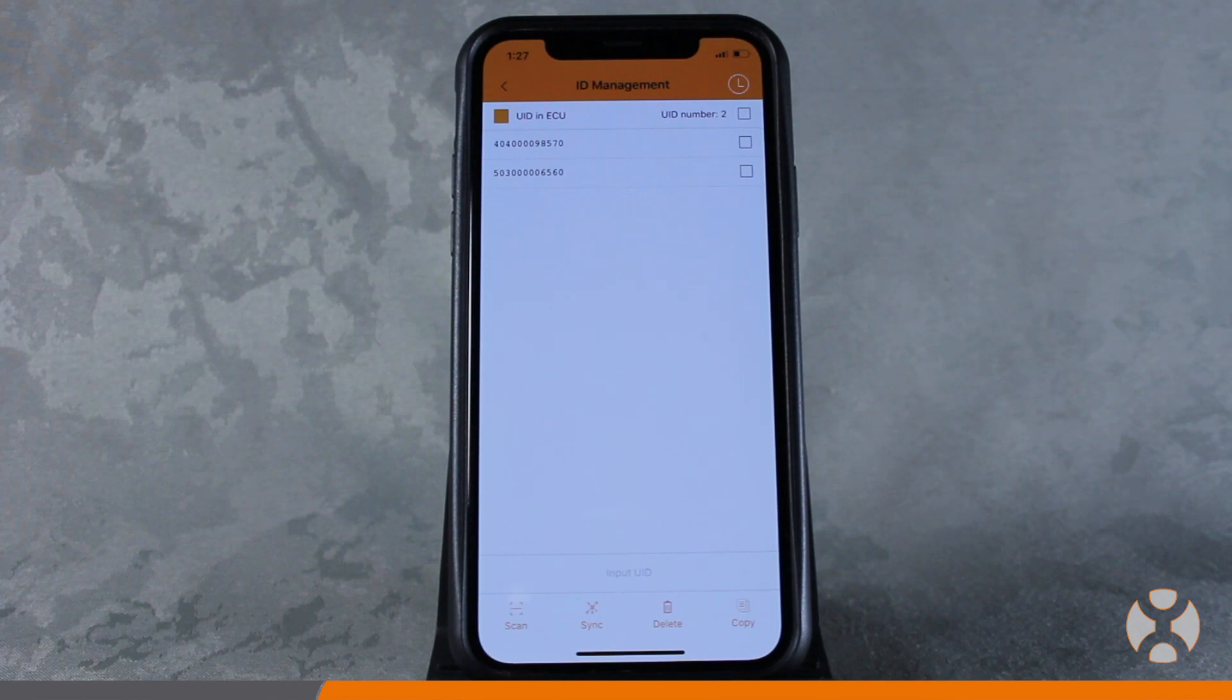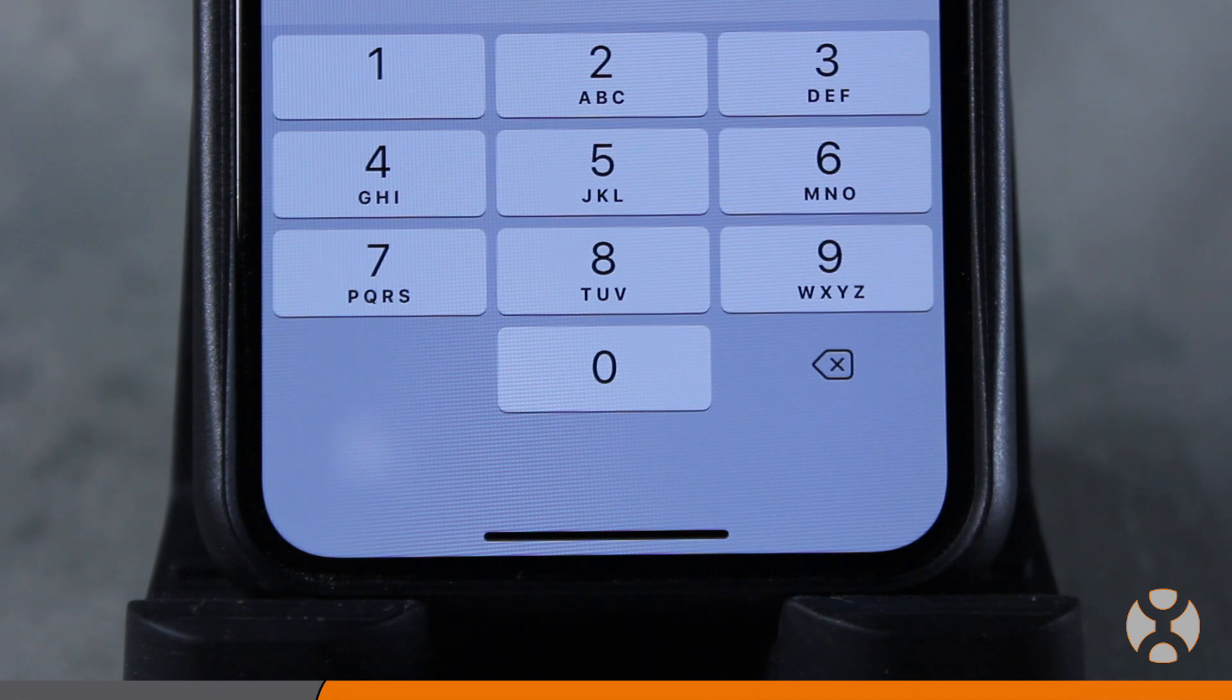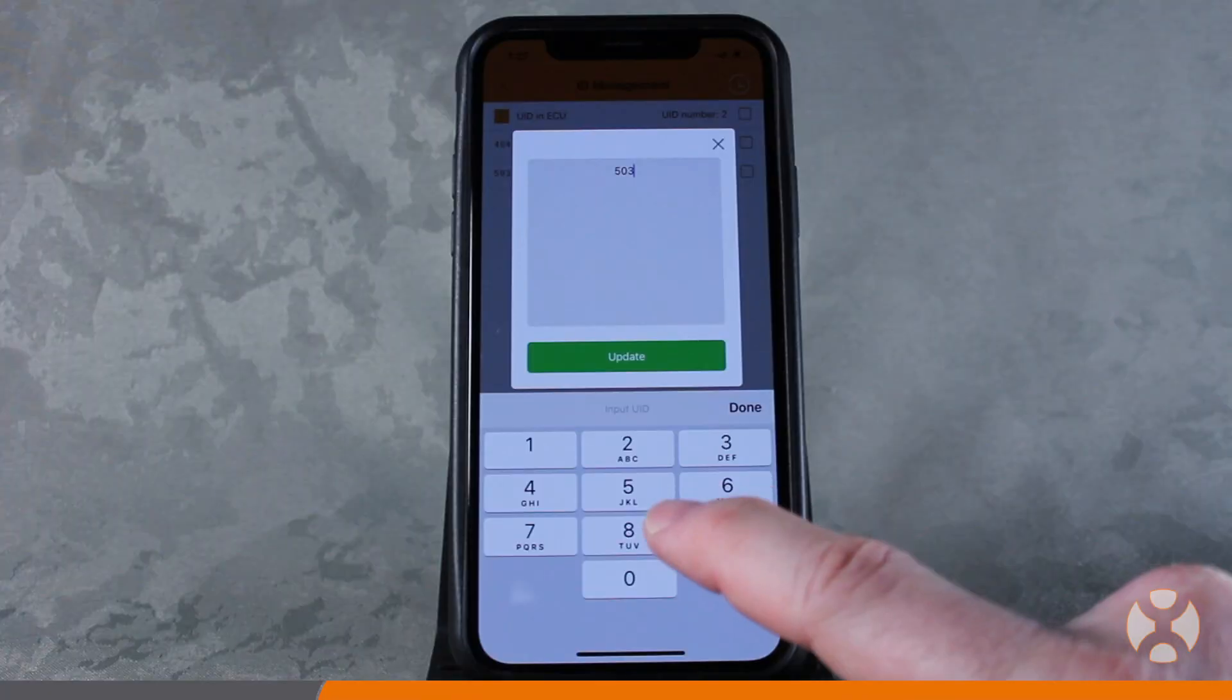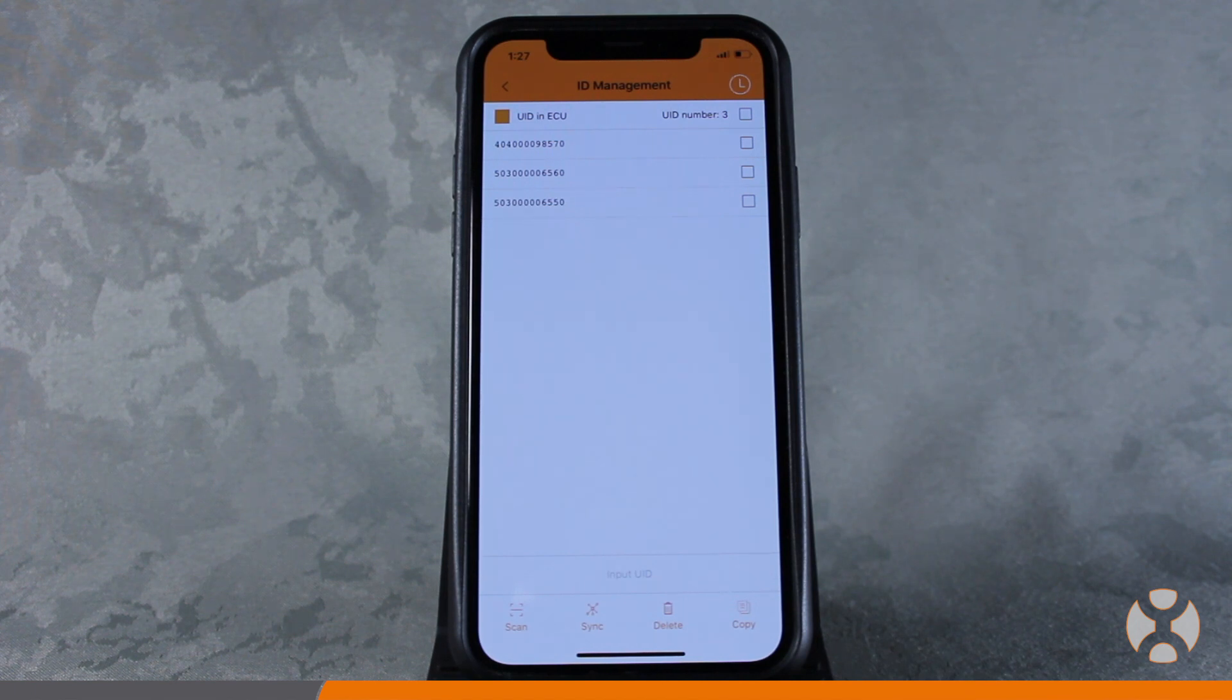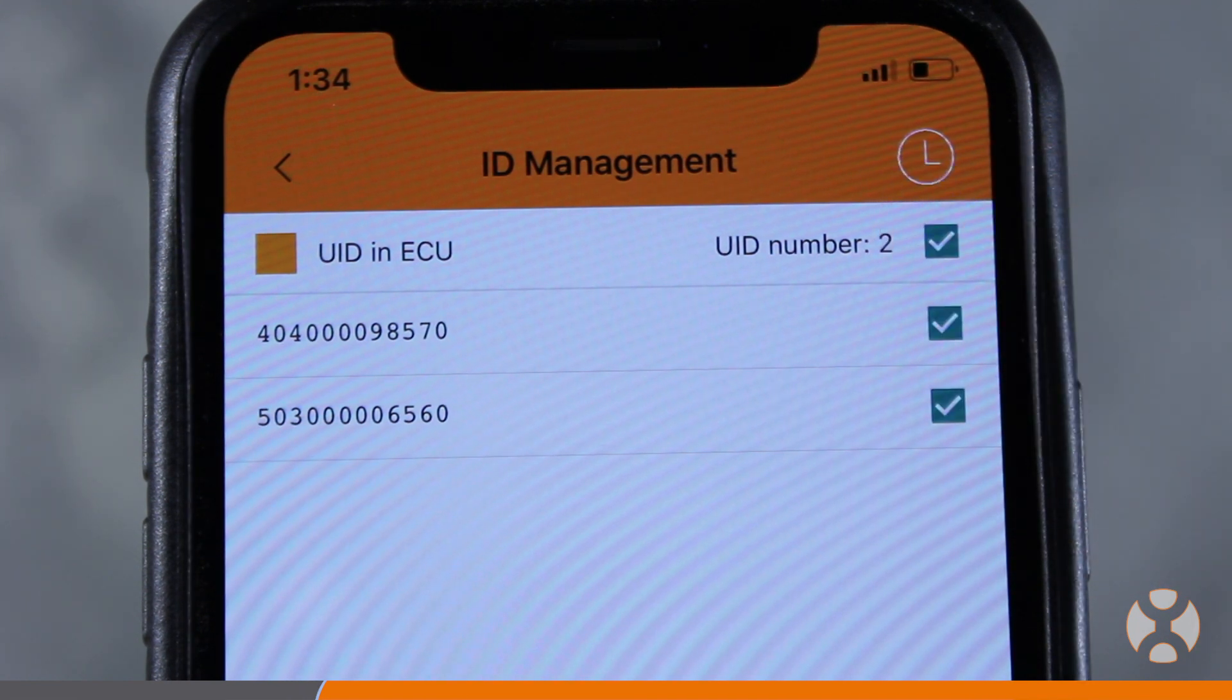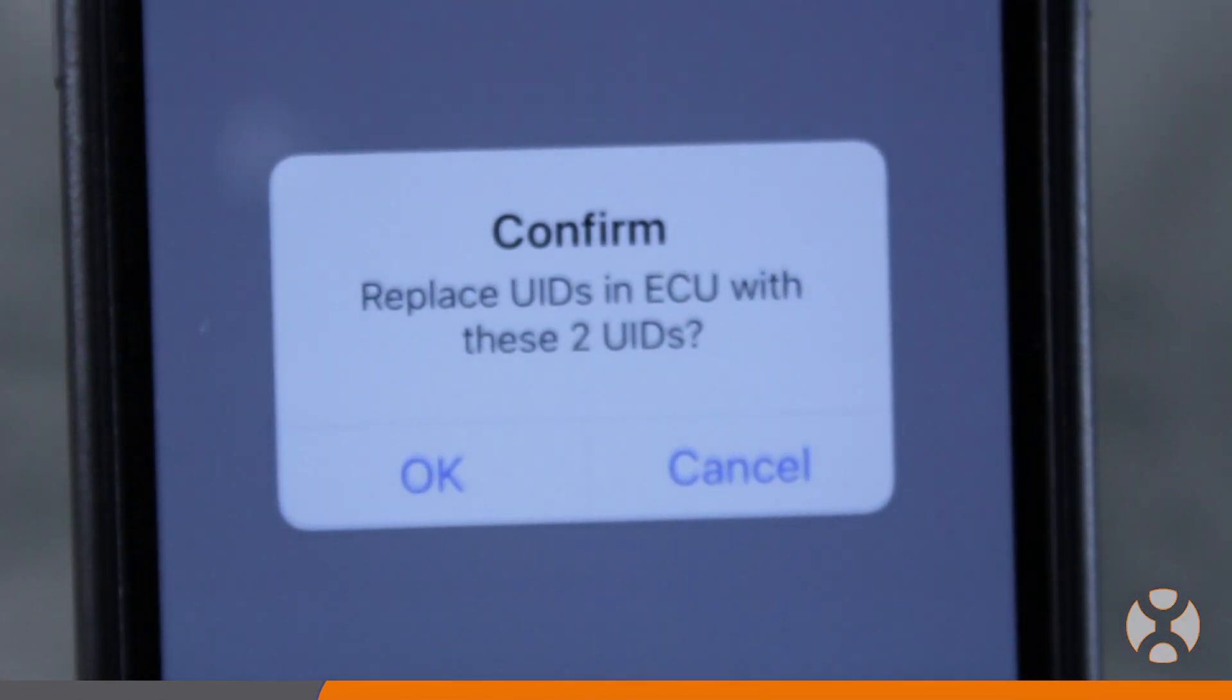To manually enter a UID number, click on the input UID field just above the bottom options and enter the 12-digit microinverter UID number. Add the new UID to the list. After all the array UIDs appear on the ID management screen, select them using the box to the right of each UID and touch Sync.